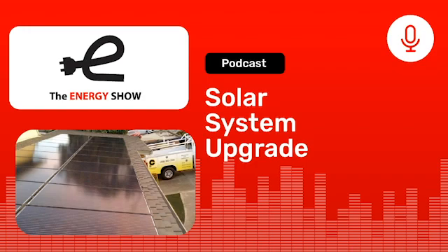I did a quick analysis on this thing called the California Solar Initiative Calculator. This is a good calculator that you can use to see how much energy you're going to get out of a system with various configurations. I took a look at a typical 7,500 watt rooftop solar system. That's kind of average, and it's tilted at 15 degrees. If that system is tilted at the ideal 15 degrees due south, it'll generate 11,200 kilowatt hours a year.